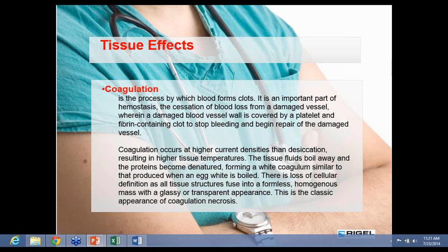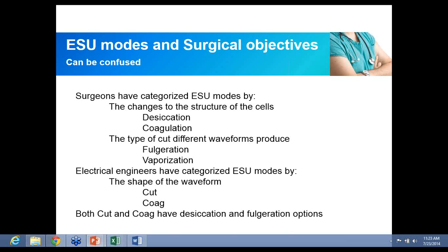Electrical engineers and biomeds, we categorize ESU modes by the shape of the waveform. A cut waveform is a pure sinusoidal, and a coag has a very unique waveform, which I will show you shortly. But both coag and cut have desiccation and fulguration options. So it's important that you keep in mind when you're talking to a surgeon versus when you're talking to someone in tech support about what is cut and what is coag. A pure cutting current is very easy to recognize. It's a pure sinusoidal waveform. There's no variations in the frequency or in the amplitude.